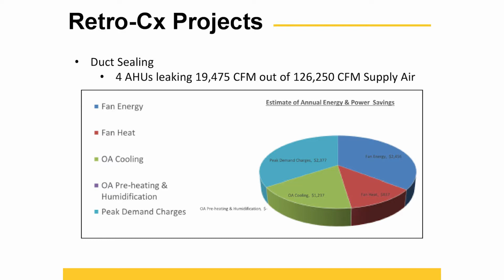We did a pre-tab on it and then rolled through with a duct cleaning and duct sealing project. You've read the ASHRAE articles, seen a couple of them. I don't know if this was the Aeroseal product or not, but something that met the same ASTM standard. We were able to claw back 20,000 CFM by cleaning and sealing up that old ductwork. It did involve mechanical sealing where seams had busted, but then going through and doing the aerosolized sealing to that ductwork, we were blown away by that number, frankly blown away.